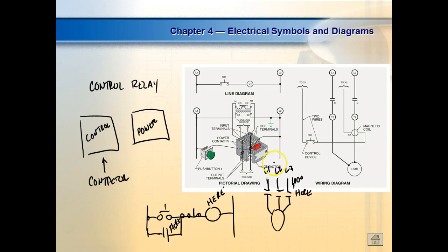Now over here, this could be 440, right? You understand, running a 300 horsepower motor. This would be in the power circuit. So a contactor could have contacts in the control circuit, but it's going to have contacts over in the power circuit. So this would be the power circuit. Normally, this is the way circuits run. This over here might be 26 volts AC. Over here, it could be controlling 440 volts, right?